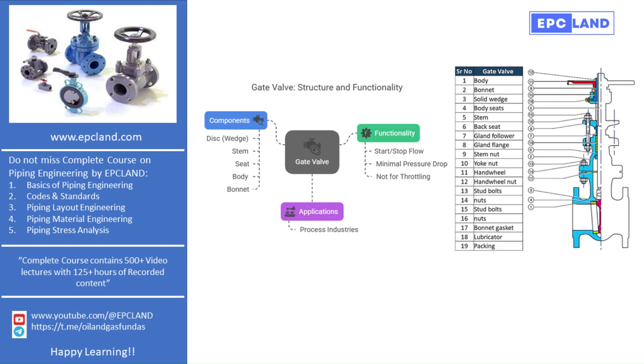Now let's talk about how the gate valve operates. Gate valves are linear motion valves. This means the gate moves in a straight line — up to open the valve and down to close it. When fully open, the gate disc is completely out of the way, allowing fluid to flow with almost no resistance. That's why the pressure drop across a gate valve is very low when it is fully open.